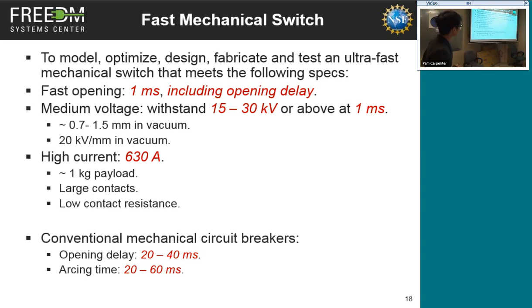So then we talk about this fast mechanical switch. This is our target. We try to open the mechanical switch to a certain gap in 1 millisecond, and that should include the opening delay. So we are talking about the total time for this mechanical operation. We are targeting medium voltage level, so 15 to 30 kilovolts or higher. We're using vacuum as the dielectric, considering that 20 kilovolts equals 1 millimeter in vacuum. So we are talking about 0.7 to 1.5 millimeters in vacuum. We need to achieve that in 1 millisecond, including the opening delay.